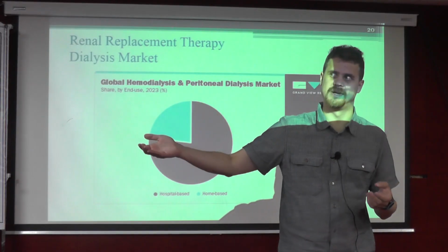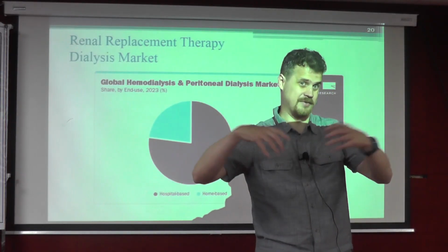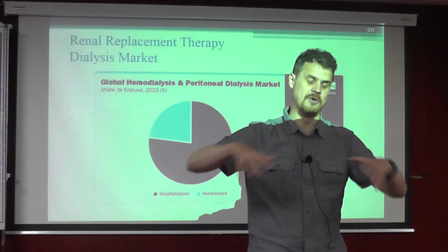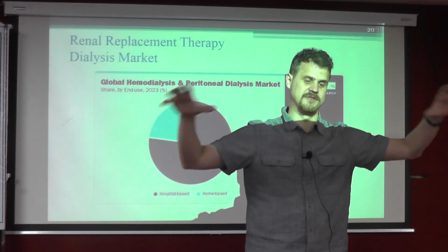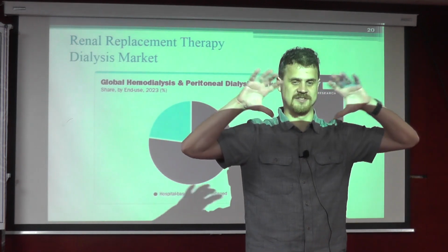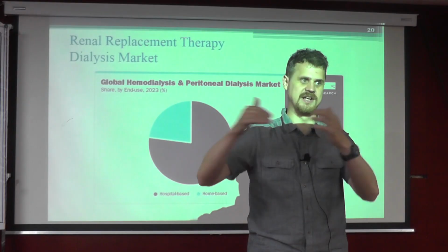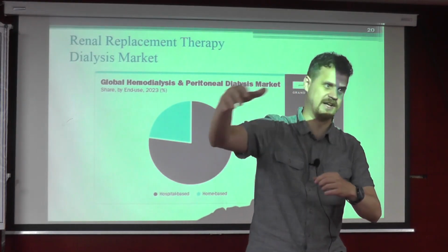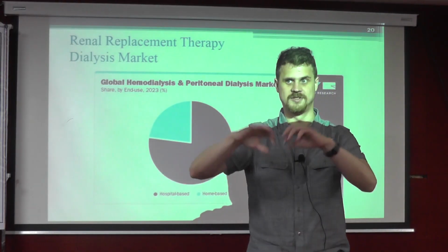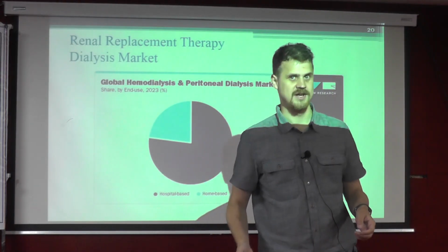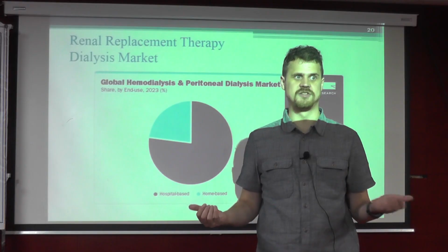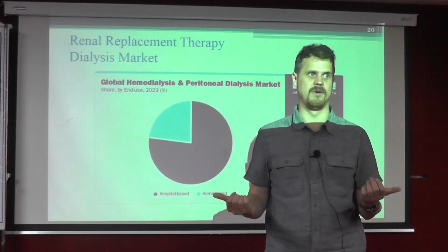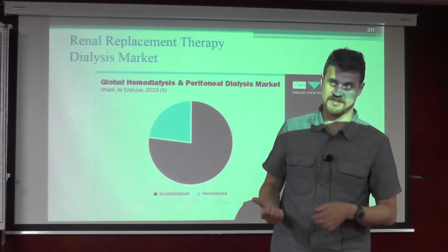In the case of automatic peritoneal dialysis, we need to make sure that all circuits of this peritoneal dialysis system are sterile. They have no connection with the outer medium, so there is no way to contaminate any pumps or tubules inside of that system. So the contamination issue is a very big problem in terms of peritoneal dialysis.